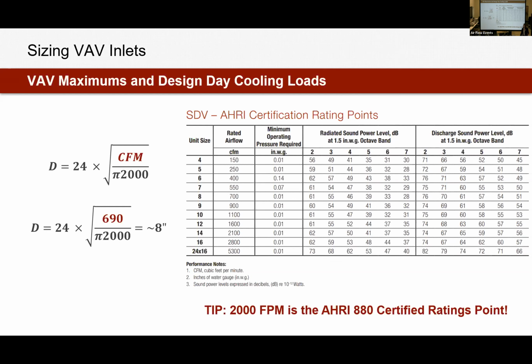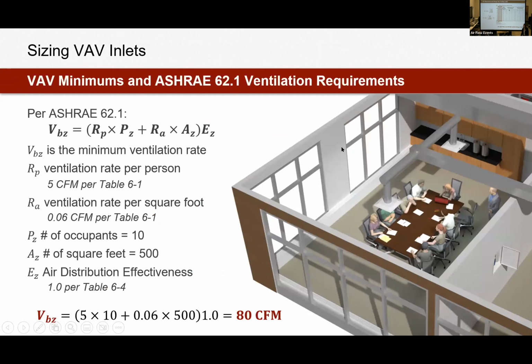Now, just because this is what the math shows us, we need to check with a manufacturer's catalog to make sure that that's actually possible. So here's an example of a screenshot from a catalog. We can check that size 8. We can look at the size 8 inlet valve here. The manufacturer is recommending that max airflow be no greater than 700 CFM. And again, that is our 2,000 feet per minute point. So sending 690 CFM through a size 8 box will keep us below that 2,000 feet per minute. Kind of just a double check there through the catalog.